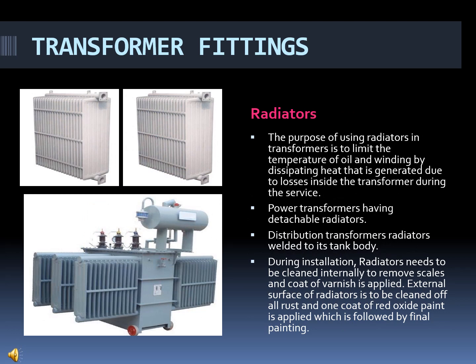Now the next fitting is radiators. What is the purpose of using radiators in the transformer? Let's understand. The purpose of using radiators in the transformer is to limit or control the temperature of the oil and winding by dissipating the heat that is generated due to the losses inside the transformer during service. There are two types of transformer: one is a power transformer, another is a distribution transformer. Power transformers are large and have detachable radiators. Distribution transformers are normally small in size and hence the radiators are welded to the tank body.